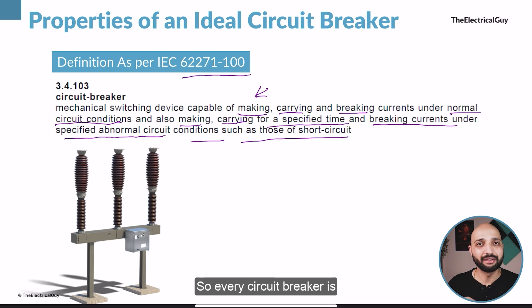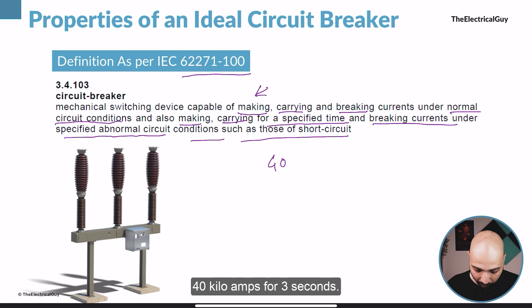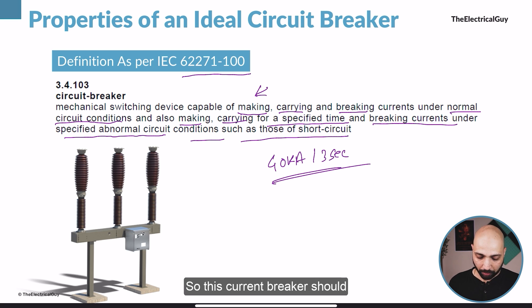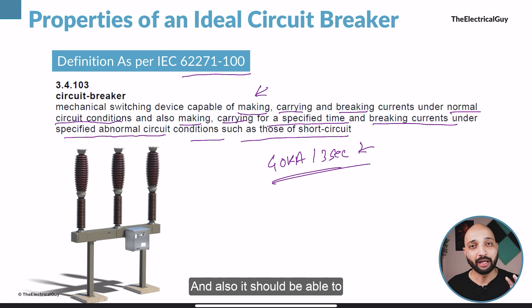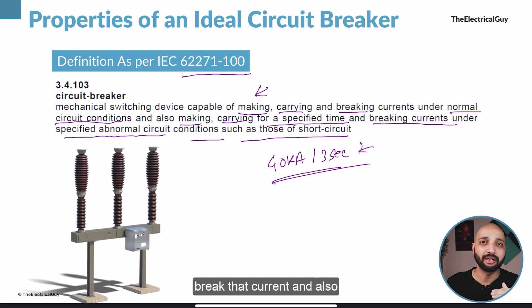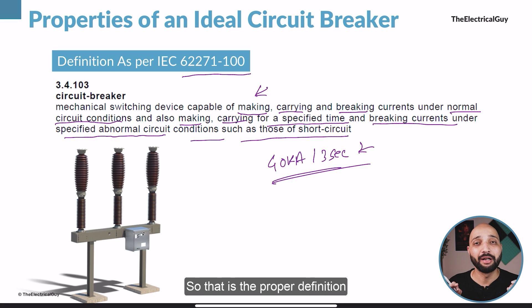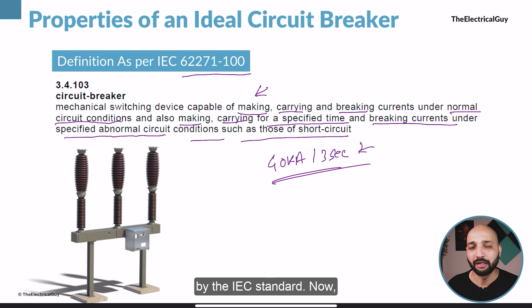Every circuit breaker is rated with some short circuit capacity — for example, 40 kilo amps for 3 seconds. The circuit breaker should be able to carry that current for the specified time of 3 seconds, and it should also be able to break and make that current. That is the proper definition of a circuit breaker as given by the IEC standard.